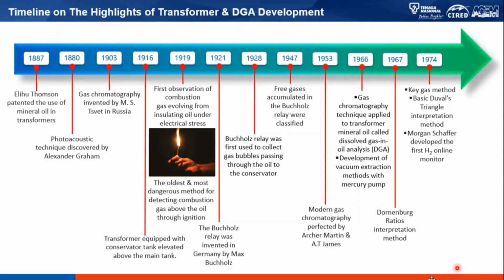Let me proceed quickly. One very interesting thing to relate to DGA is the invention of the conservator tank in 1916. Before that, a lot of transformers used free breathing, with an air cushion or nitrogen cushion on top of the main tank. But once they realized the oil surface was in contact with the environment over a huge surface area, they invented a small tank on top of the main tank.